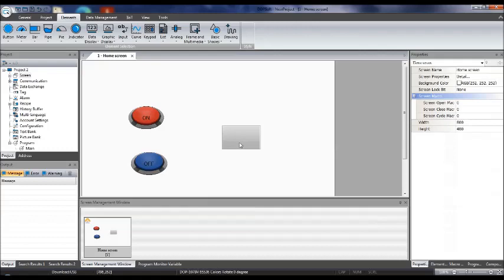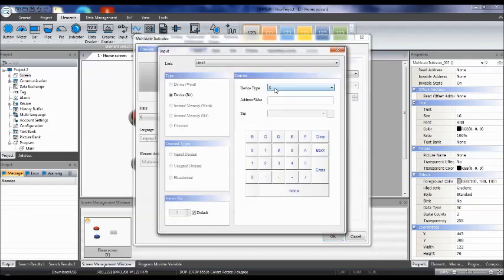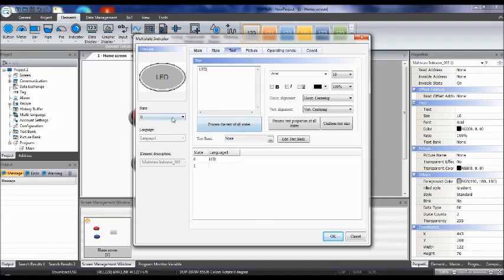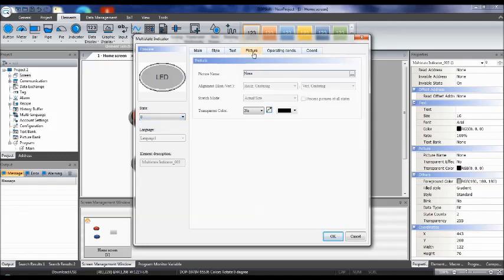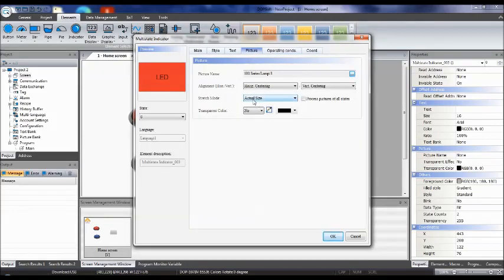For the indicator (output), double click on it. Set the address to M0 and press Enter. Set the Style to Round. In Text, label it 'LED' for both states. For Picture, click the three-button option, go to the 100 series Lamp option — select red for state zero (off) and green for state one (on). Click OK and set Stretch Mode to Stretch All.